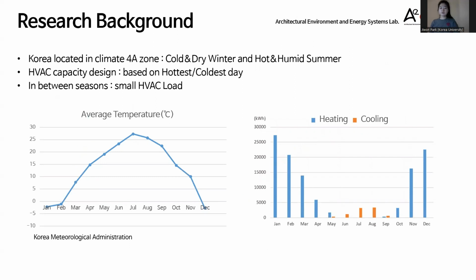This research focuses on the Incheon region in Korea as the building location. Korea is categorized as a 4A climate zone, which has cold and dry winters and hot and humid summers. Usually, the capacity of heating and cooling equipment is determined based on the coldest and hottest days. So during the transitional seasons, the load is significantly lower than on the coldest or hottest days, resulting in the equipment operating at low PLR and consuming more energy.